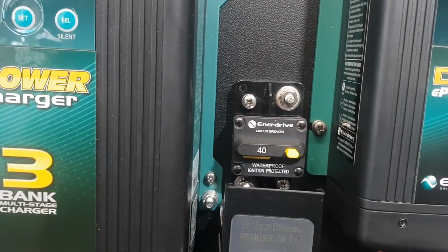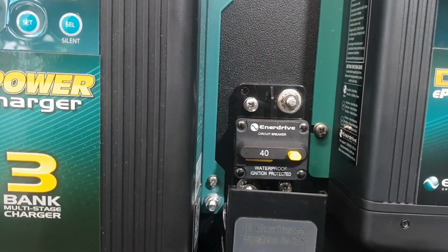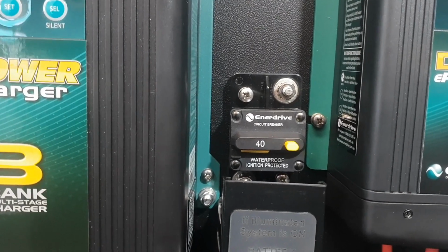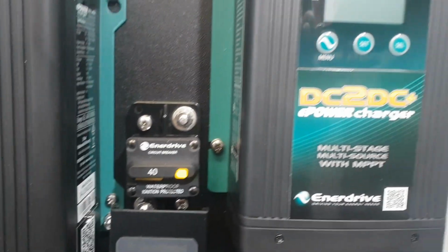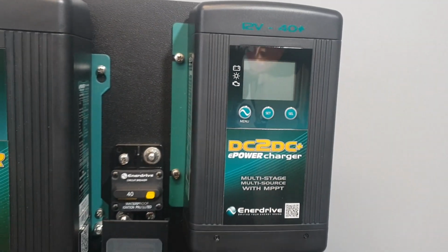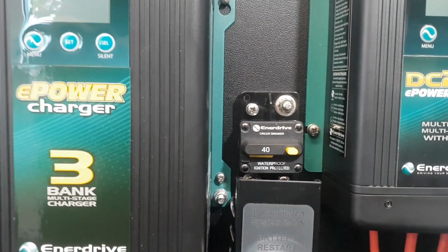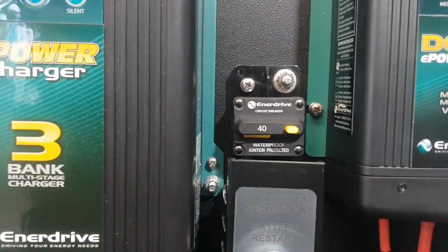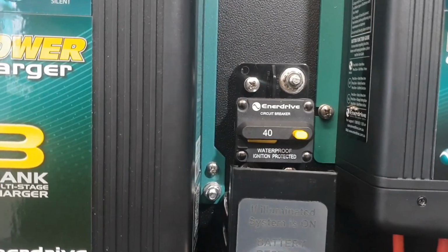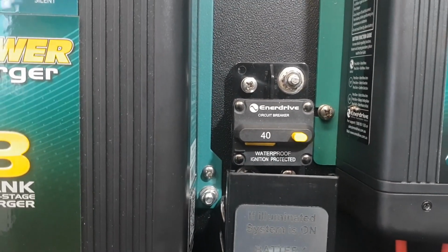This breaker is added as part of your solar system, so this breaker is wired directly to the solar input of the DC to DC. It makes for an easier installation, but it certainly makes for a more serviceable system. You can press the button on that breaker to isolate your solar.